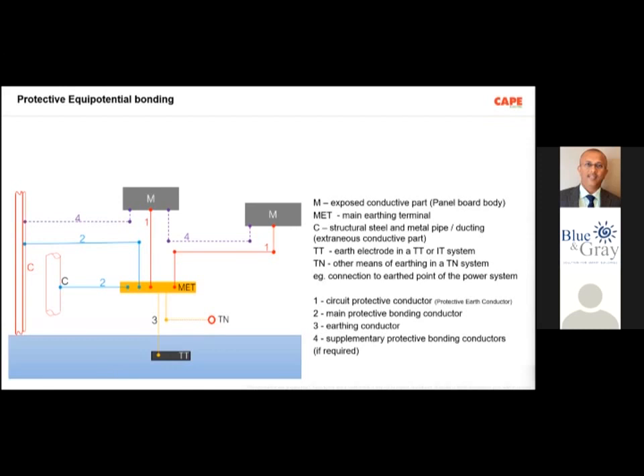So for easy understanding, if we look at the regulation, don't think that this is required. This is actually not required because we are not going as per TT. We are supposed to go for the TN system. So basically, all the metal parts in your building must be interconnected, and this is called protective equipotential bonding. Now the safety auditor should make a test for it, just to ensure that the touch voltages are lesser than the limit which is explained in the standard. But unfortunately, in most of the buildings in India, including high-rise buildings, this safety measure itself doesn't exist. If the safety measure doesn't exist, where do you test?